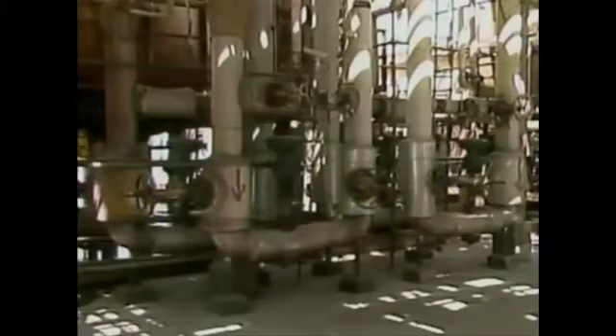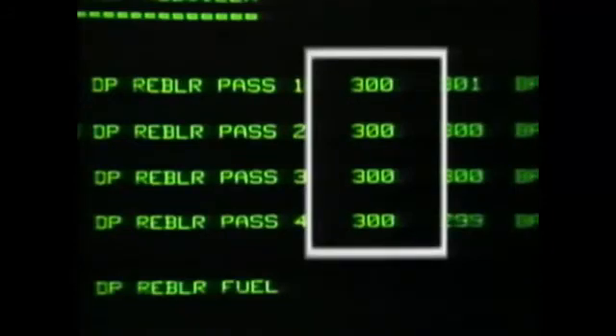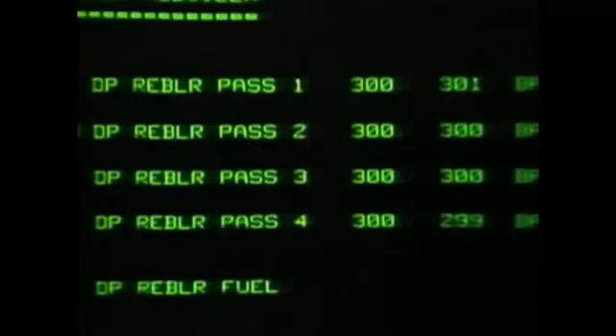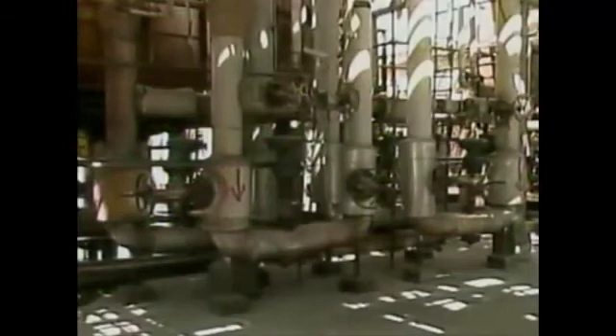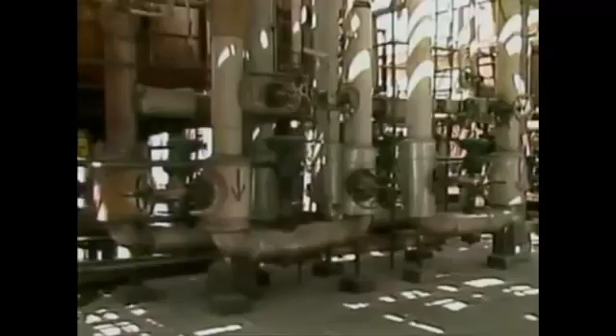Each valve controls one pass, and there's a set point for each pass — usually the same for each pass. Maintaining the same flow rate allows the process fluid to be heated to the proper temperature more efficiently. If the flow rate deviates from set point in any pass, the control valve for that pass is repositioned automatically to increase or decrease flow and return the flow rate to set point.